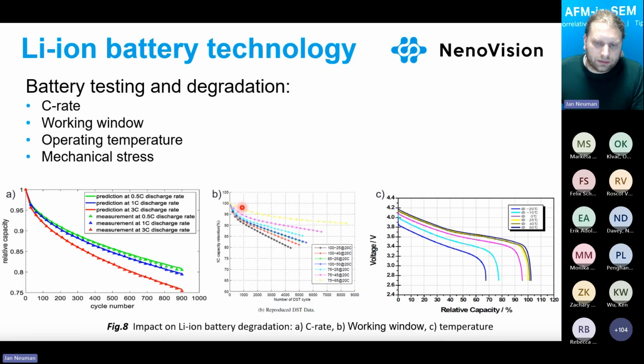Another thing that influences battery degradation is the test working window. If we cycle the battery in the full range from 0 to 100%, the degradation will be much faster compared to cycling in a shallower range, for example between 65 and 75%, as shown on the yellow curve.